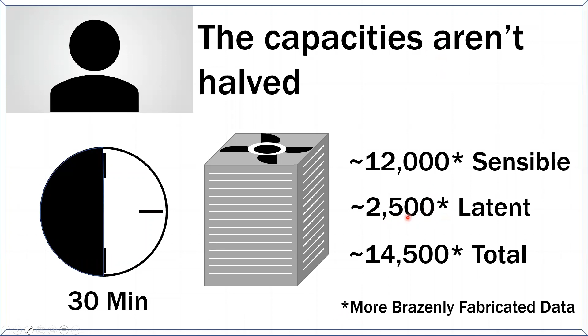And there's a slide explaining this. That first stretch, I'm calling it 15 minutes, call it whatever you want, depends on the unit, actually starts off doing literally zero humidity control. Nothing—it's just not cold enough. And then there's a point where it hasn't reached its target temperature, where it starts to do a little humidity control. And then the humidity control kicks in.